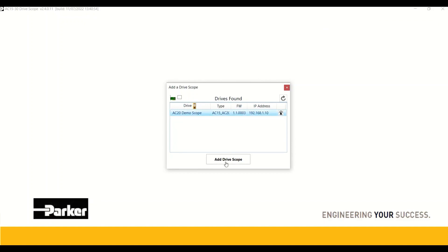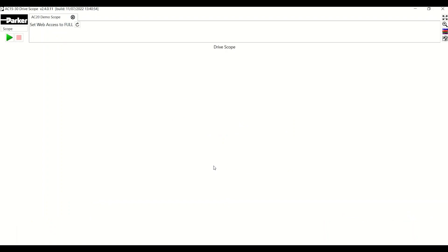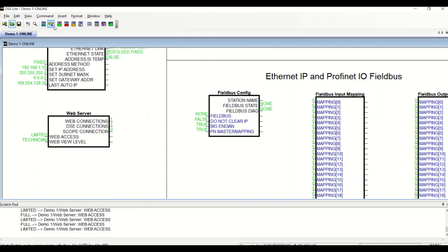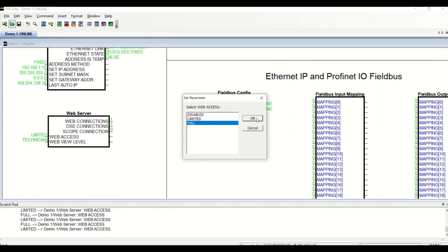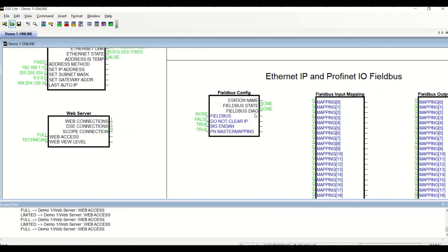I have selected it, and now I can connect. Arriving on the Scope page, there is very little displayed, because Web Access, which is a parameter of both AC15 and AC20, needs to be set to Full. To do this, you can either go via DSE Lite, as I am doing here, or from the drive directly. Note also that I can be online via DSE Lite and via the scope simultaneously.